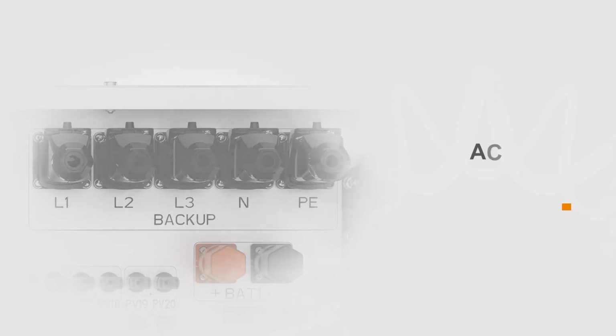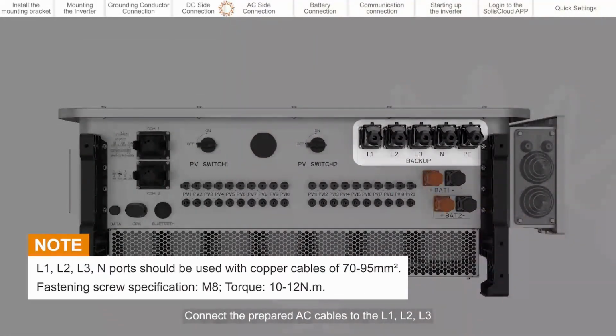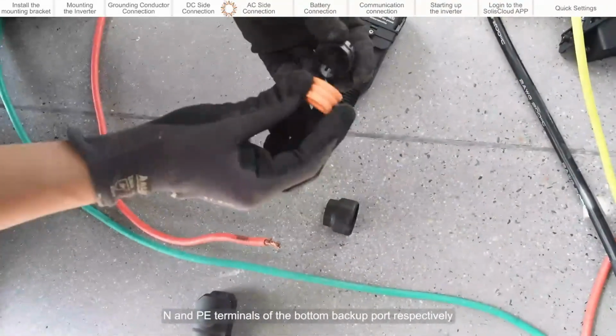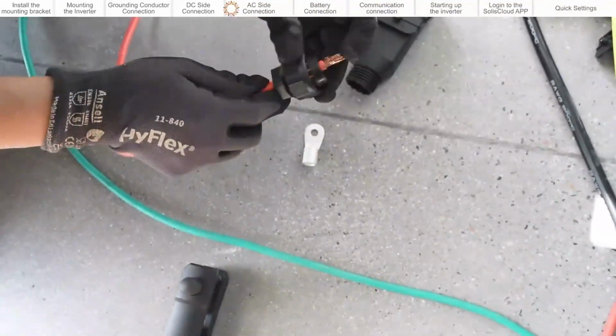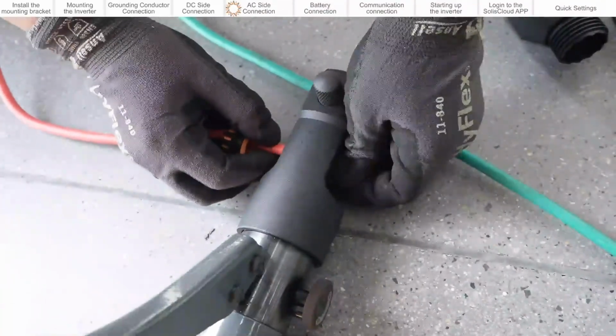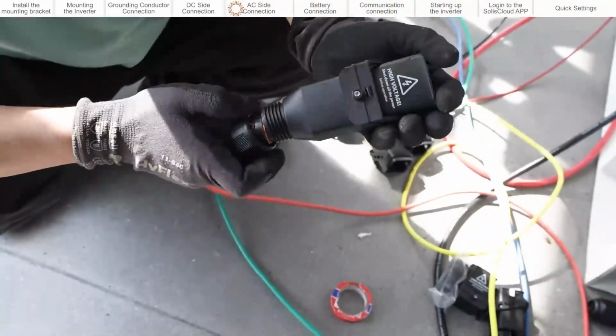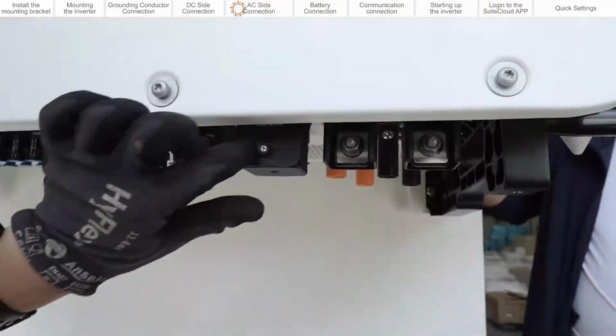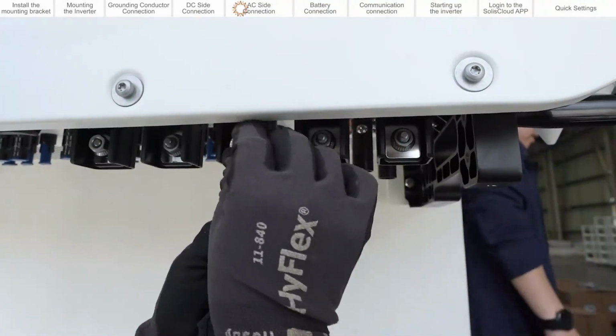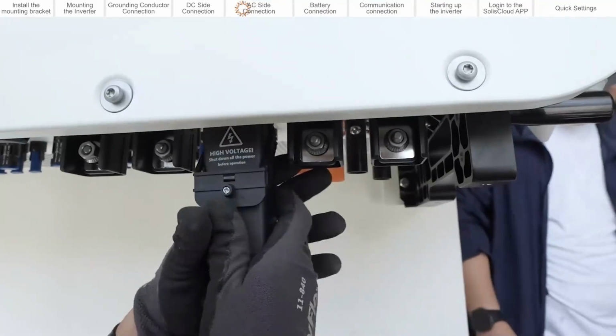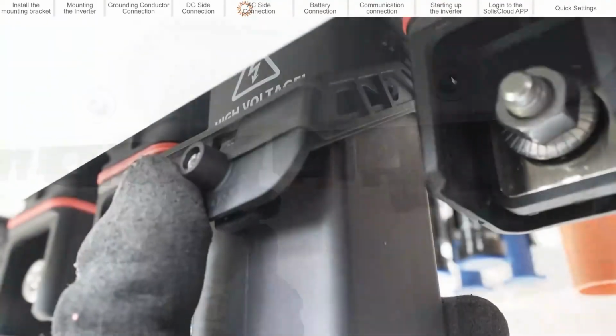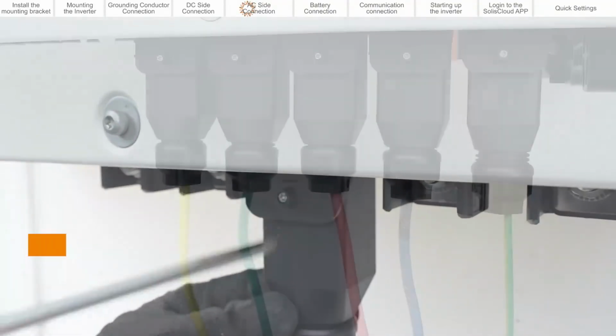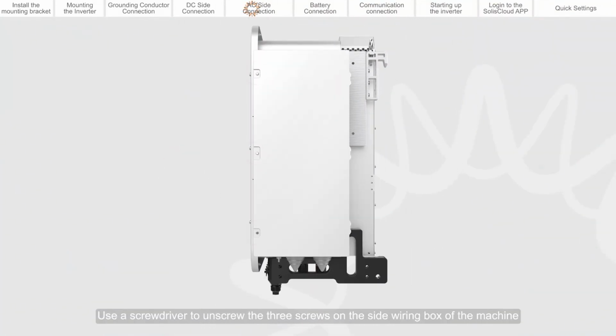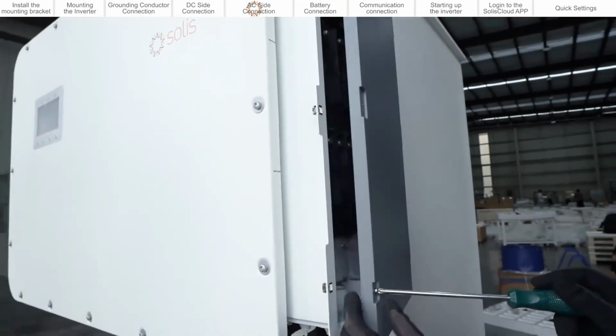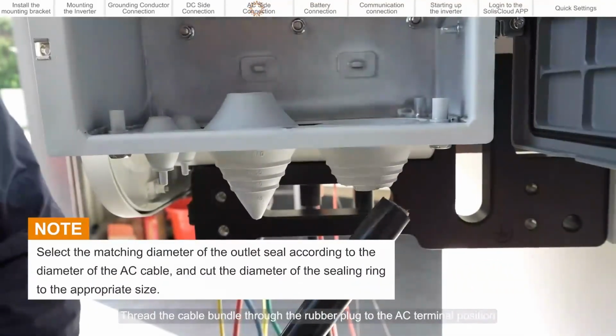AC side connection. Connect the prepared AC cables to the L1, L2, L3, N and PE terminals of the bottom backup port respectively. Use a screwdriver to unscrew the 3 screws on the side wiring box of the machine, and then open the wiring box cover. Thread the cable bundle through the rubber plug to the AC terminal position.